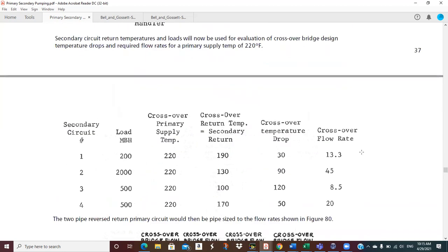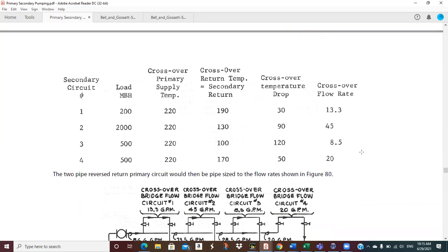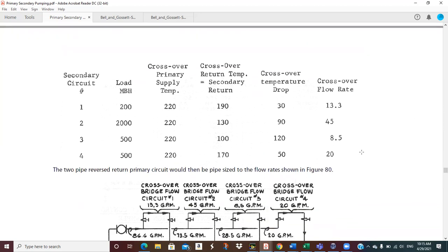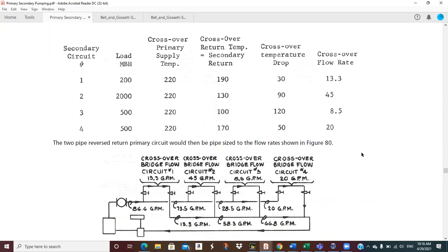Then for each one of these, it's pretty easy. You've got your crossover temperature drop. I'm putting in at 220 and coming out at 190, and I've got 200,000 BTUs an hour. So 200,000 divided by 500, the constant, divided by 30 is 13.3 GPM. So I've got to take 13.3 GPM out of my crossover loop, or put it into my crossover loop. I've got to take it up into my secondary. I haven't shown all the secondary stuff up here. I'm just showing the crossover.